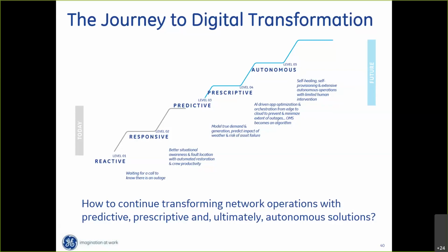So when you keep a human in the loop, you're going to be greater than 5 minutes, right? The reliability is not going to be nearly as good as it would be if you take the human out of the loop and do closed loop control. So it can be done. Many utilities are doing it today, and it works. You put the logic out there and test it first in manual mode to make sure all the recommendations make sense. We fine tune the logic. When we have full confidence in the logic, then we close the loop on it. First, we may close the loop semi-automatic, doing upstream restoration only, with a human still in the loop at downstream, but eventually we'll want to do fully automatic and do both upstream and downstream restoration automatically.